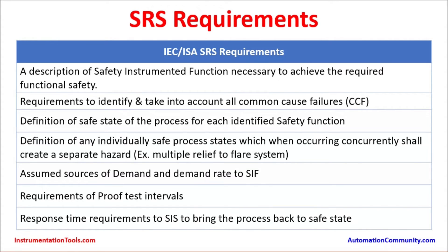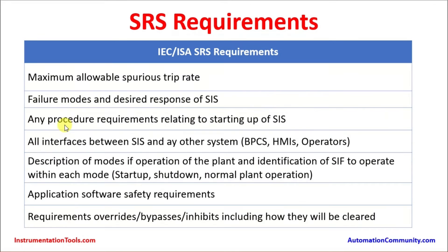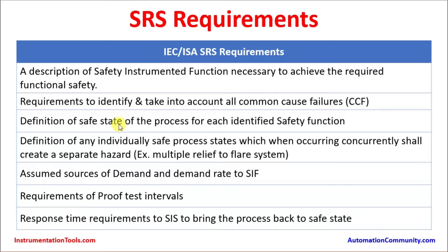SRS requirements based on IEC/ISA standards include: a description of the safety instrumented function necessary to achieve required functional safety; requirements to identify and account for all common cause failures; definition of the safe state of the process for each identified safety function; definition of any individually safe process states which, when occurring concurrently, could create a separate hazard (e.g., multiple relief to flare system); and assumed sources of demand and demand rate for each safety instrumented function.